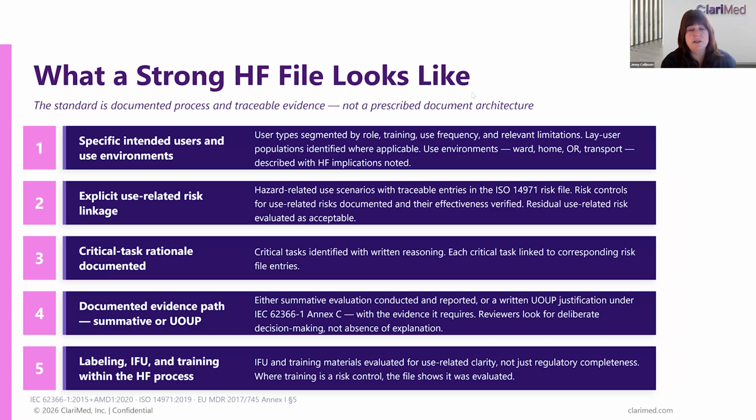If there's a missing explanation, that's just a gap that would prompt a question from a reviewer. And then the next one is you need a really clearly documented evidence path. So it's very important to be clear about the strategy to comply with 62366. A detailed usability engineering plan can help.